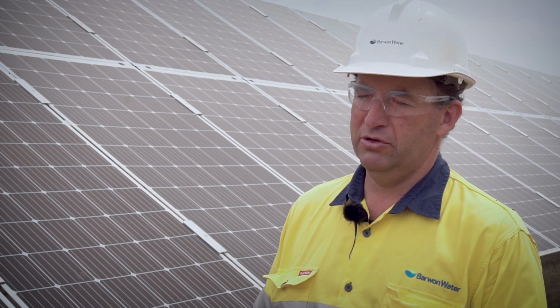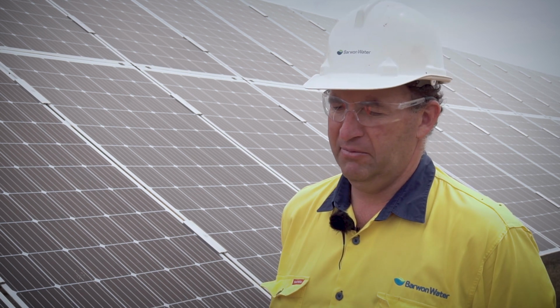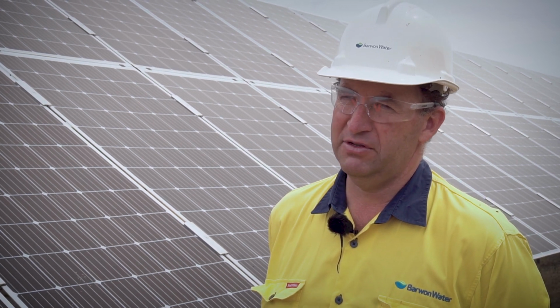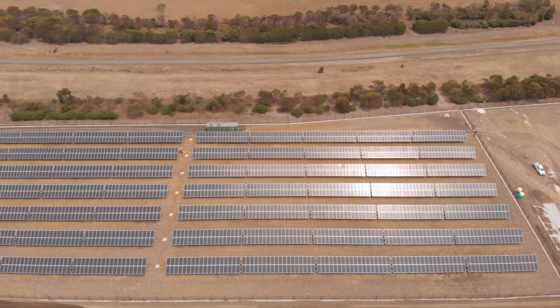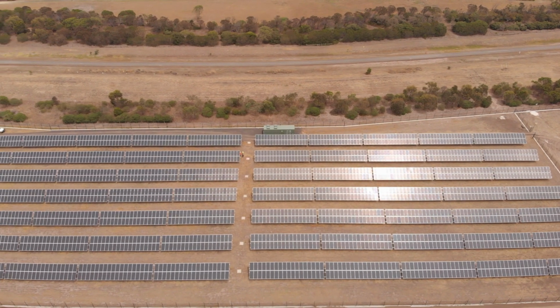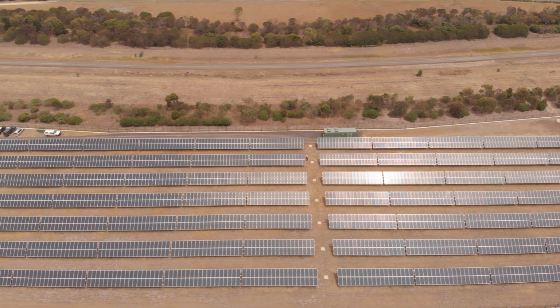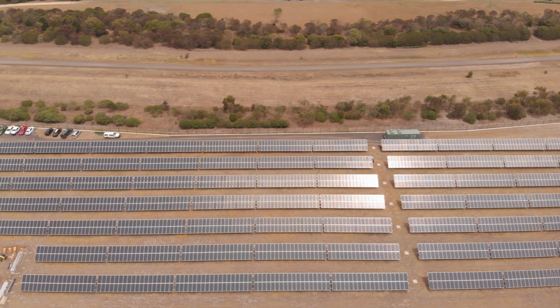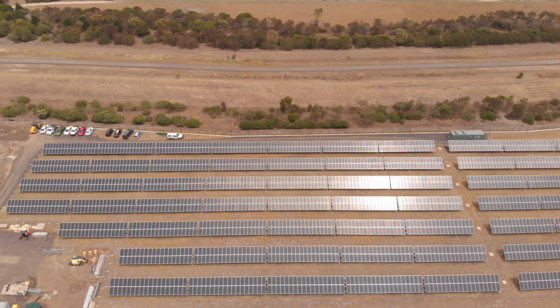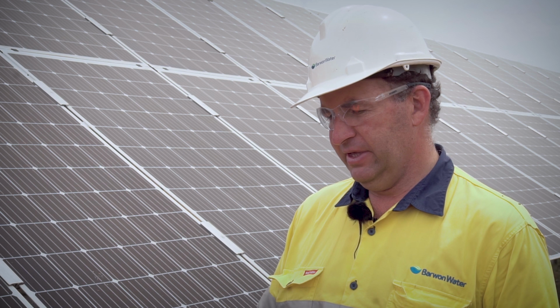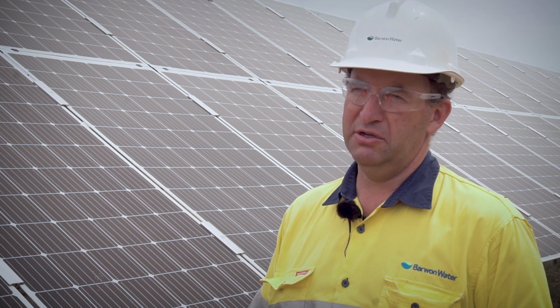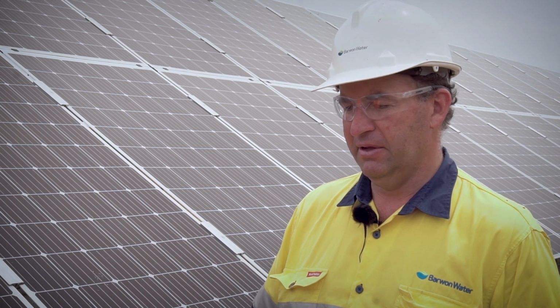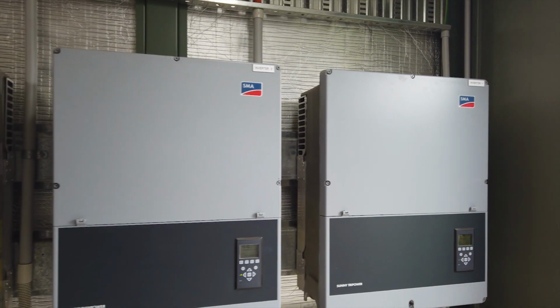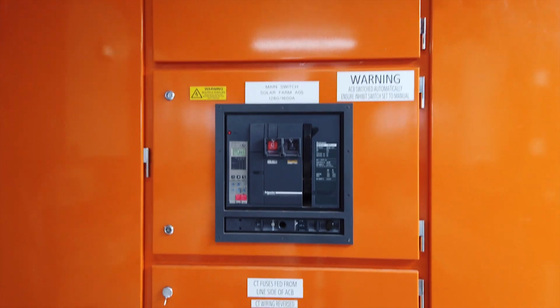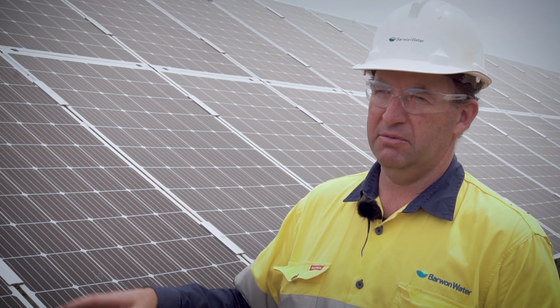We have either a 9 or a 10 string process for the panels. So we have SMA inverters, roughly 60 kilowatts each. On the high voltage side, so where we step up, it's a standard electrical transformer that steps it up from that 415 volt through to 22,000 volt. Yeah, so with our design, we've limited and balanced the proportion of DC to AC power for where it needs to be, and rather than go individual inverter rack-mounted at the string and then wiring out, we're actually wired out from the string into an inverter mounted in an enclosed cabinet.